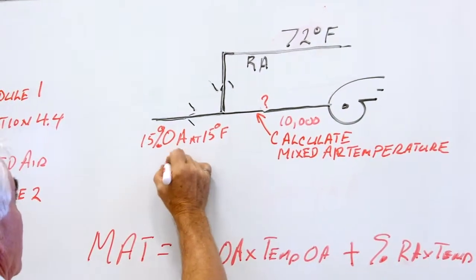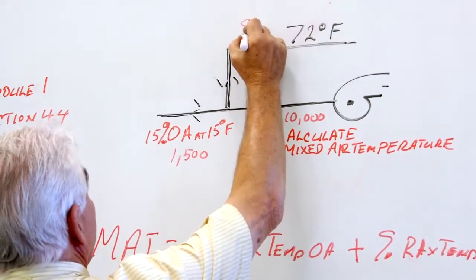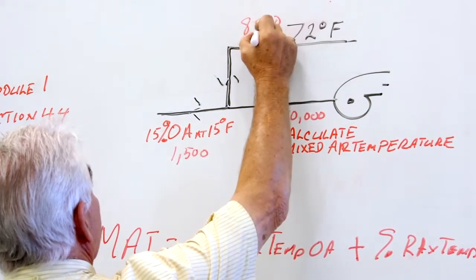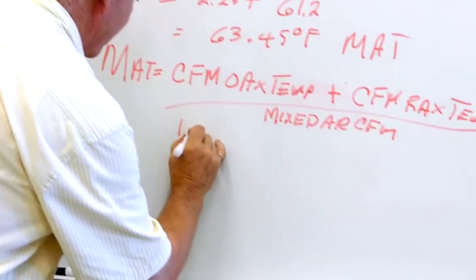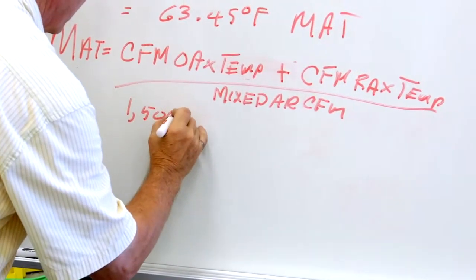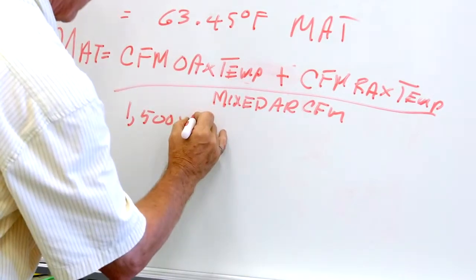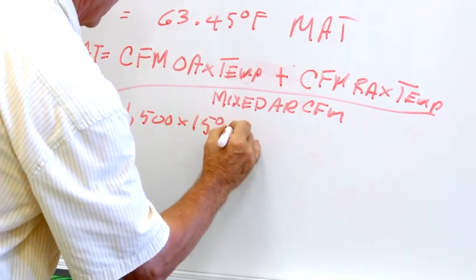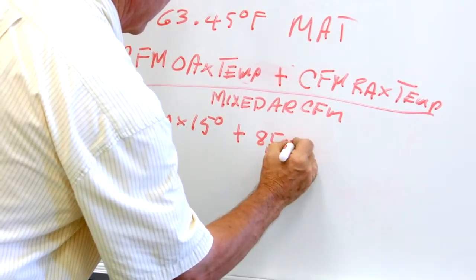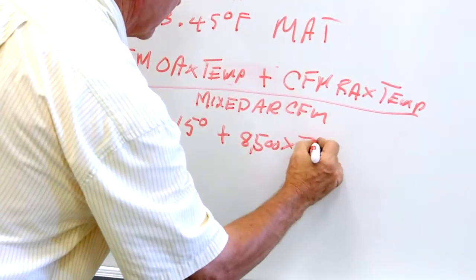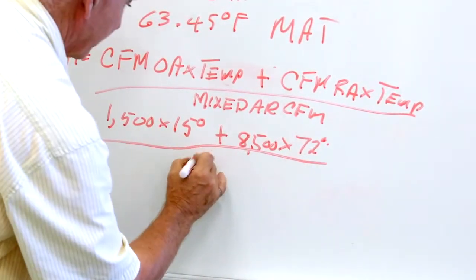15% would be 1,500 and this would be 8,500 CFM, so we'd have 1,500 times 15 degrees, plus 8,500 times 72 degrees, divided by 10,000.